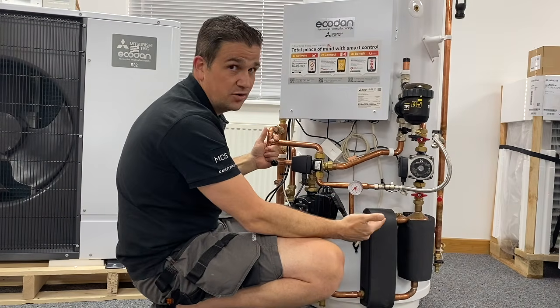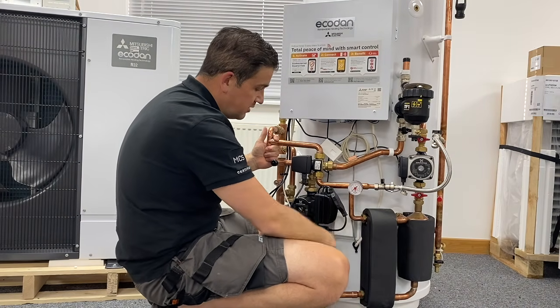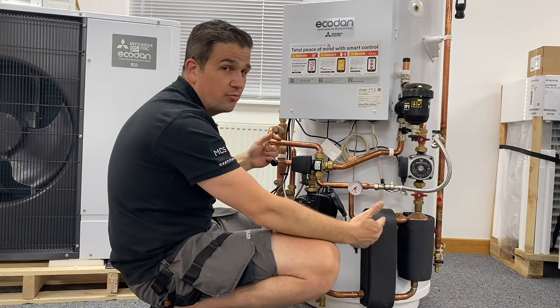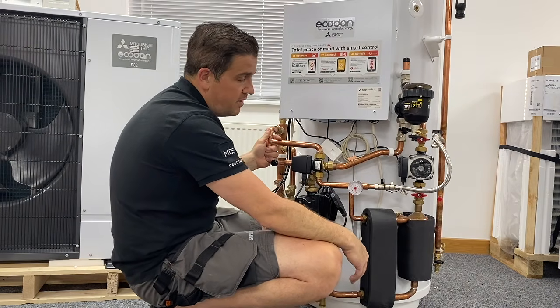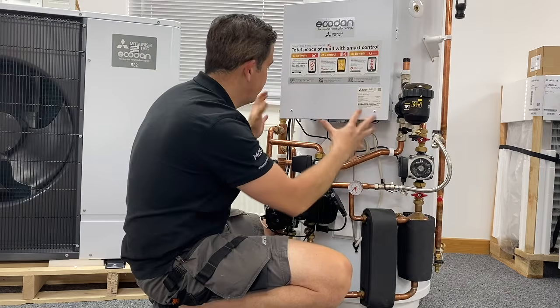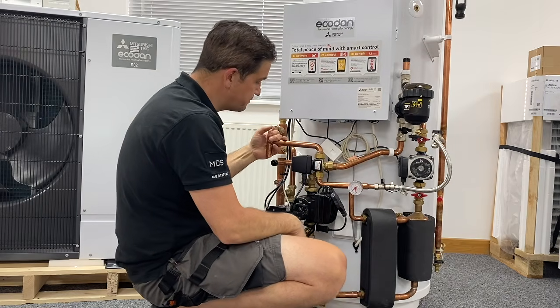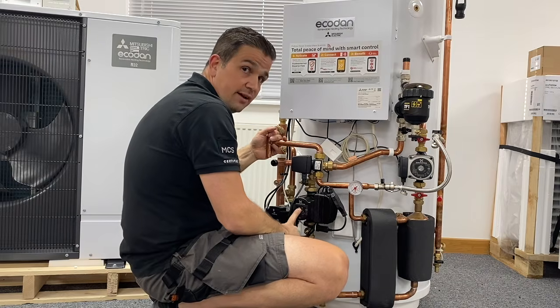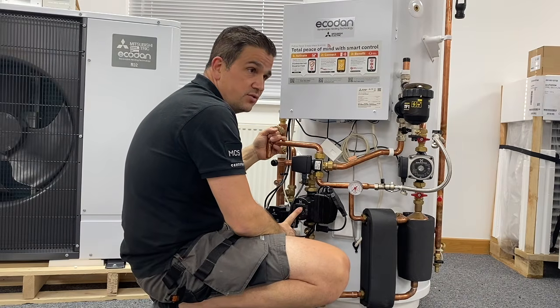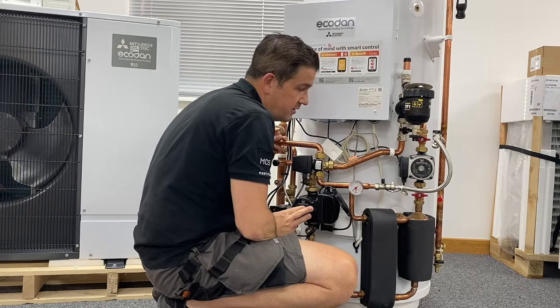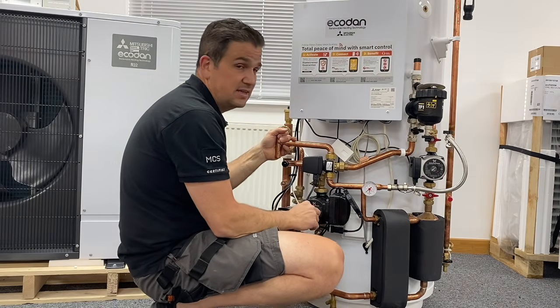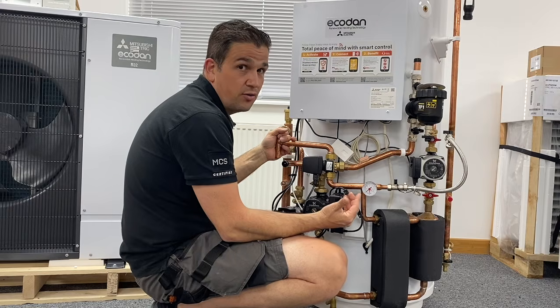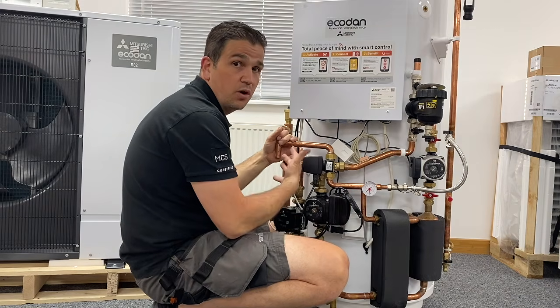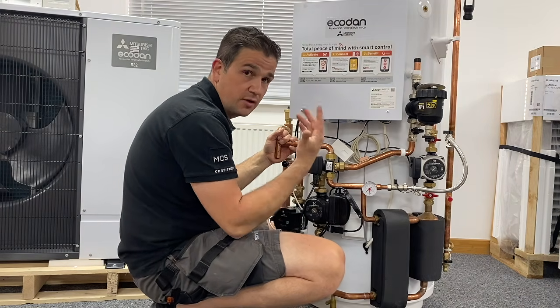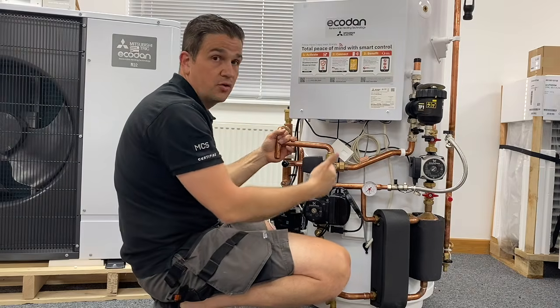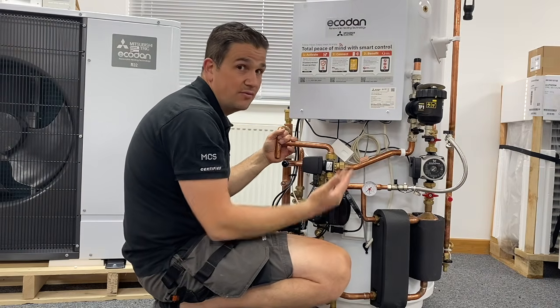Typically this is a standard unit, so it will need a floor area of at least 800 by 800 mil, which allows enough room, and with everything at the front it's serviceable. There is a slimline, but that only comes in two sizes, up to about 170 litres. There is also solar ready, and we've fitted one with a solar thermal panel jointed into a second coil, and again, it works wonderfully well.